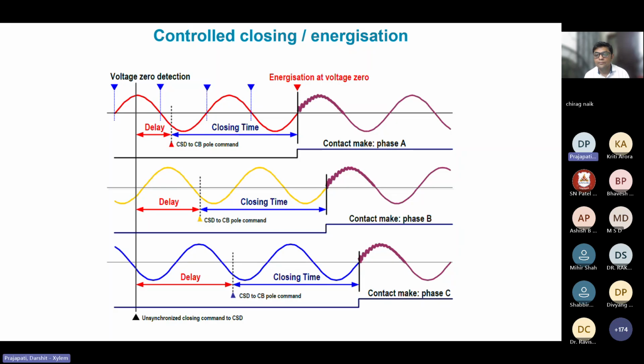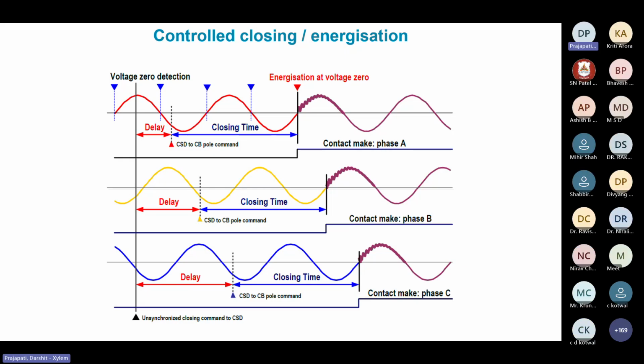So closing time, again, can be the same if all poles of the breaker are operated by the same drive, or it can be different if there are different drives or different controls for the breaker. Those different times and the delay, including the phase-wise and all the parameters we discussed earlier, the final target is achieved. For example, here it is the zero crossing of the voltage signal.